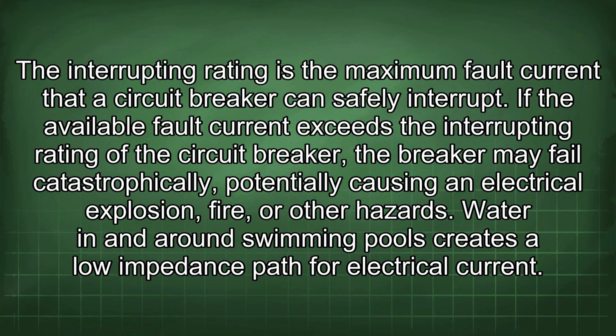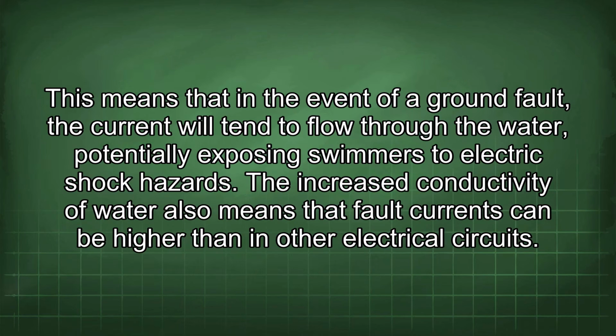Water in and around swimming pools creates a low impedance path for electrical current. This means that in the event of a ground fault, the current will tend to flow through the water, potentially exposing swimmers to electric shock hazards. The increased conductivity of water also means that fault currents can be higher than in other electrical circuits.